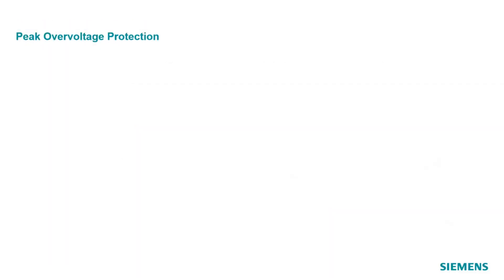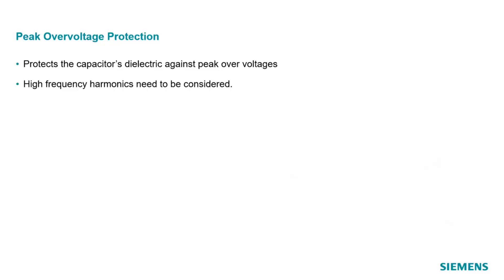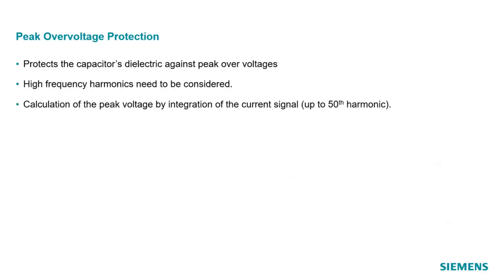The peak overvoltage protection protects the dielectric of the capacitor against too high voltages. It is necessary to also consider higher harmonics because they also contribute to the stress for the dielectric. SIPROTEC 5 with a sampling frequency of 8 kHz considers reliably all harmonics up to the 50th. Different from what someone would expect, not the voltage across the capacitor but the current through the capacitor is measured. The transmission behavior for higher harmonics of a current transformer is much better than of a voltage transformer, so the peak voltage is calculated by integration of the measured current and no additional voltage transformer is necessary.